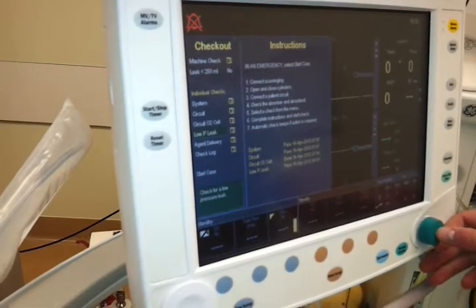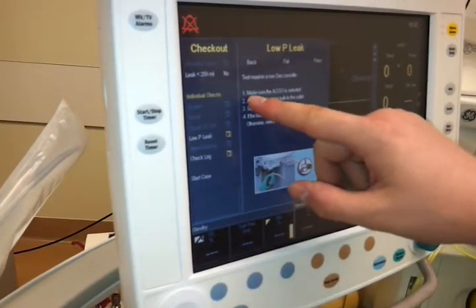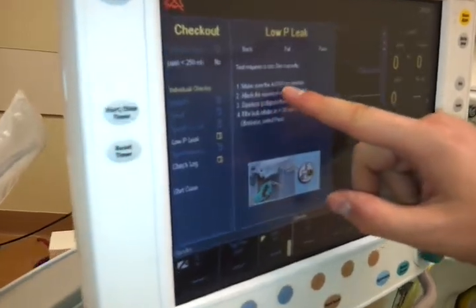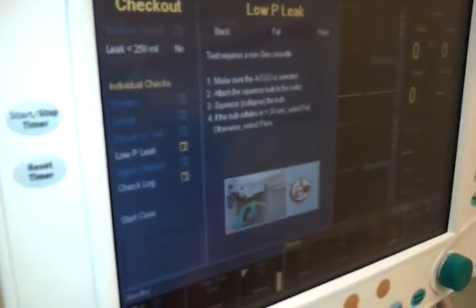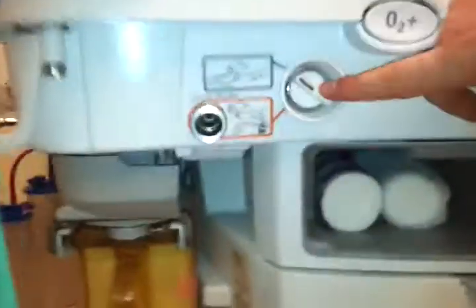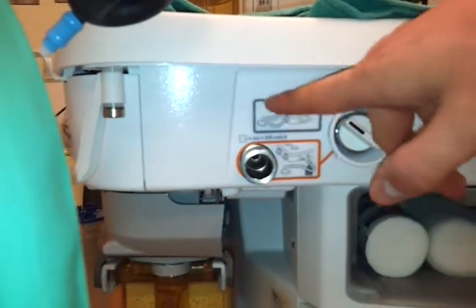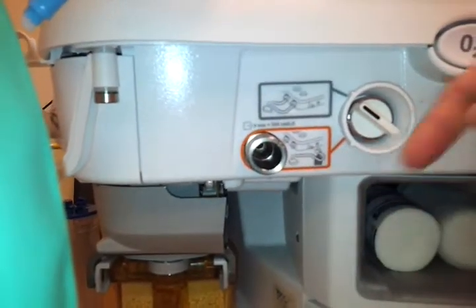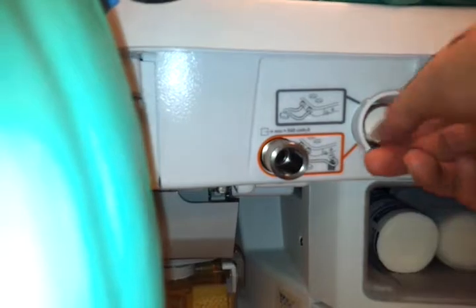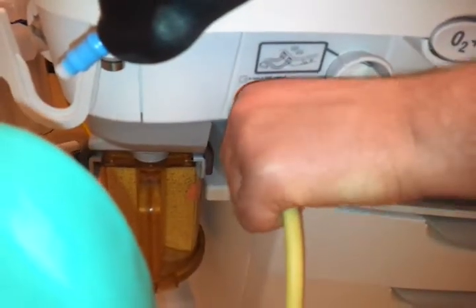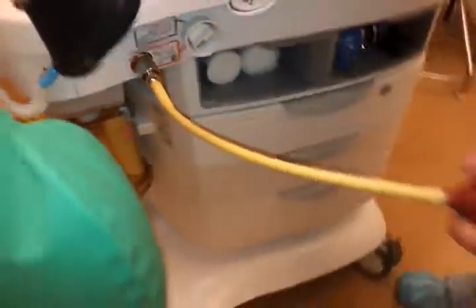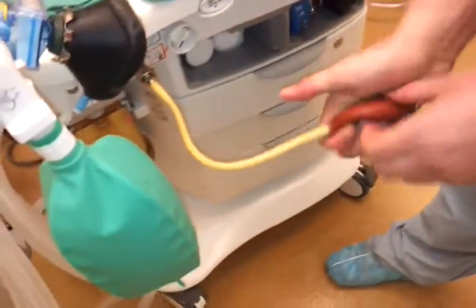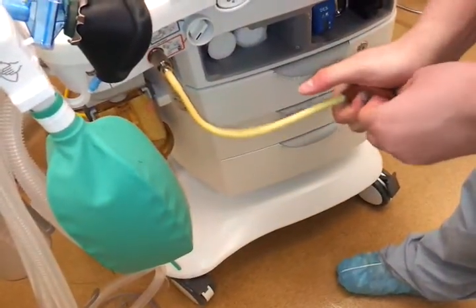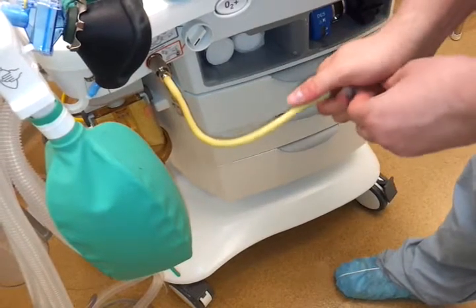So low pressure leak. You click on that. Each one of them has a list that tells you what to do. Make sure ACGO is selected. So the ACGO switch is right here. Most of the time it's set at circle, but for this you have to switch it down. Switch it down and plug in the bulb. Okay, and then basically you have to squeeze it a bunch of times until it sucks all the air out of the circuit.